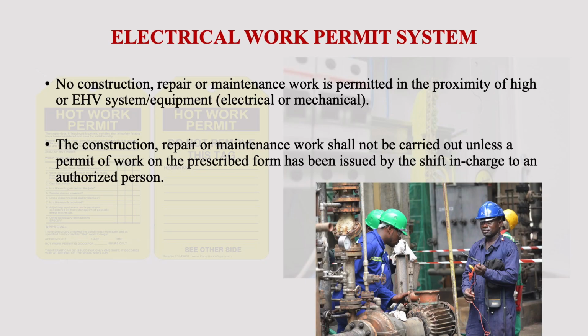So, in continuation to the specifications of the electrical work permit system, the construction, repair or maintenance work shall not be carried out unless a permit of work on the prescribed form has been issued by the shift in charge to an authorized person. The person issuing a permit to work shall ensure that the system or the equipment is made perfectly safe for working.